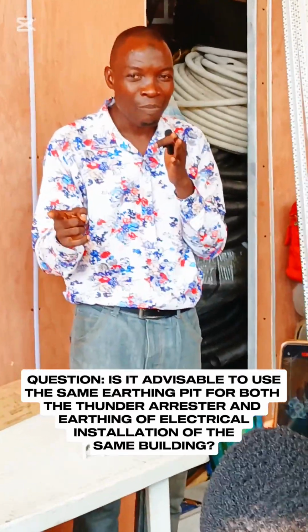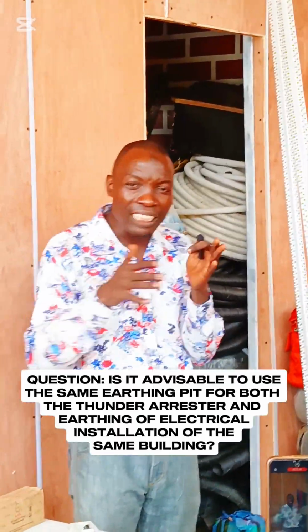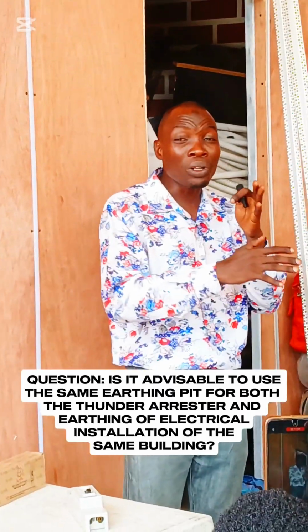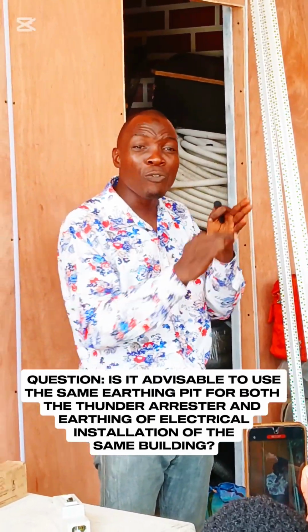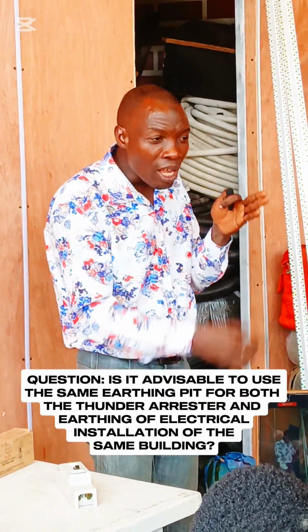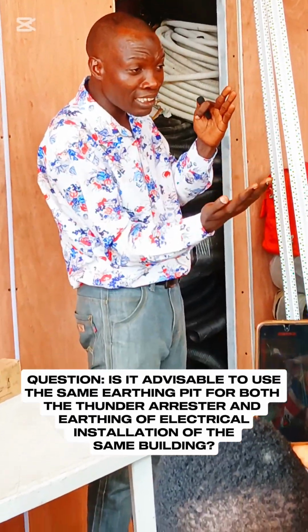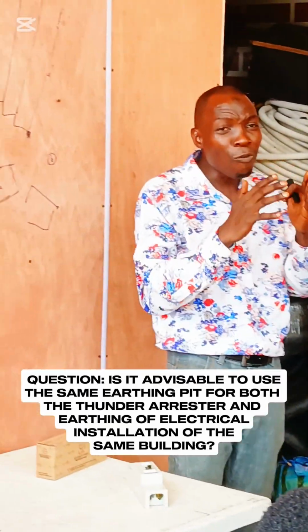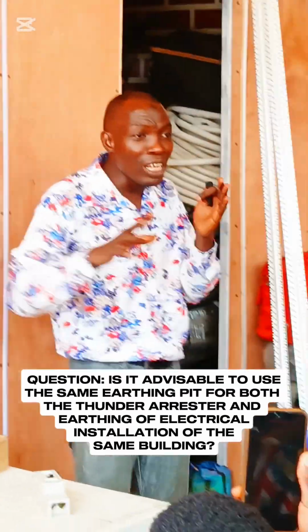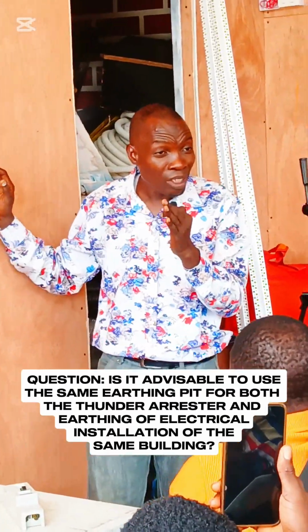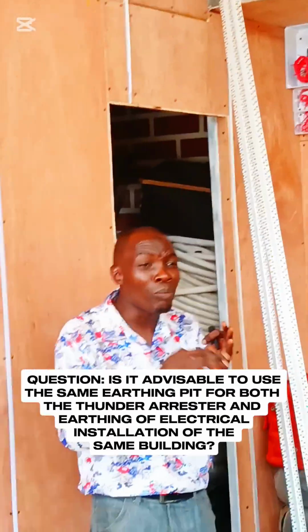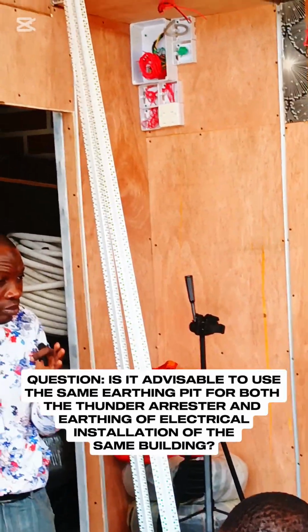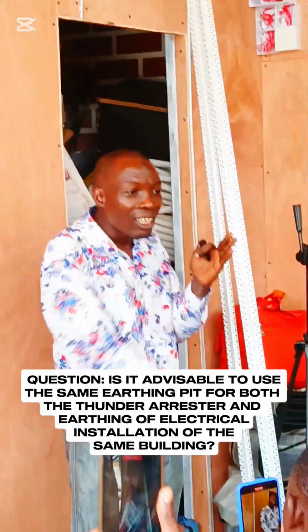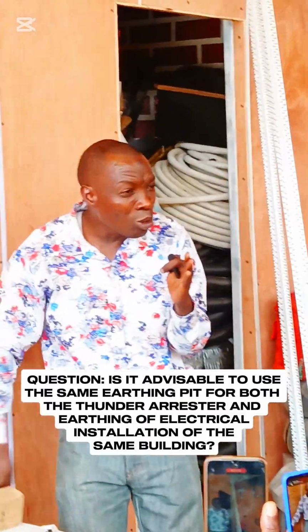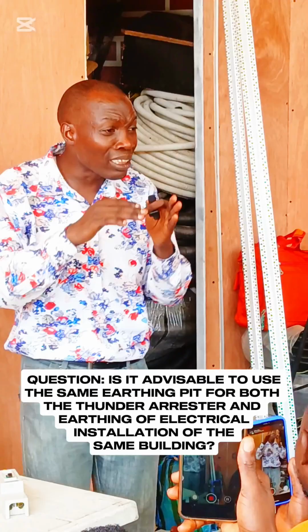Though both are earthing, the essence of earthing in electrical installation is to create a low resistance path for the fault current to flow away. Anytime there is leakage between the live and the earth, because of the severity of that leakage, if anybody touches it, it's going to feel the severity. That is why you earth all the metal framework in that installation, by connecting all the metal framework of all the appliances, sockets, distribution board, and grounding it, so you have provided a low resistance path.